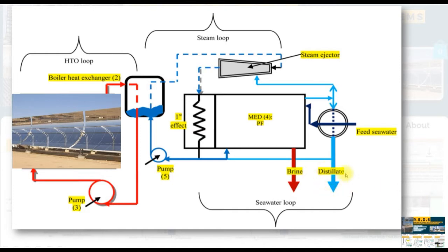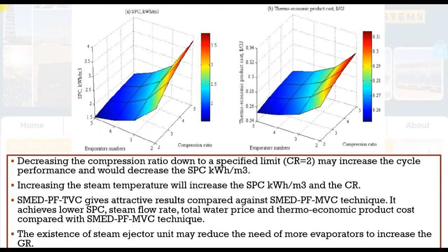We have to assign the distillate product, solar radiation inputs, top cycle temperature, and the compression ratio here in order to discover the rest of the data. If we are going based on performance analysis, decreasing compression ratio down to a specific limit — for example 2, since it's rated from 1.8 up to 6 — may increase the cycle performance and decrease the specific power consumption. Increasing steam temperature will increase the specific power consumption. Increasing number of effects will decrease the specific power consumption.